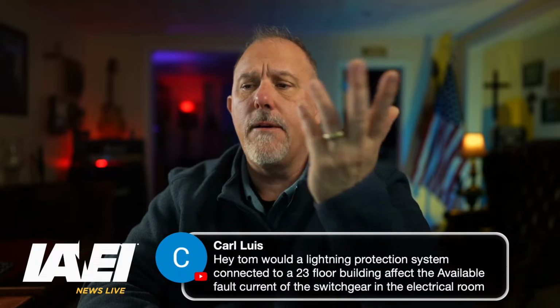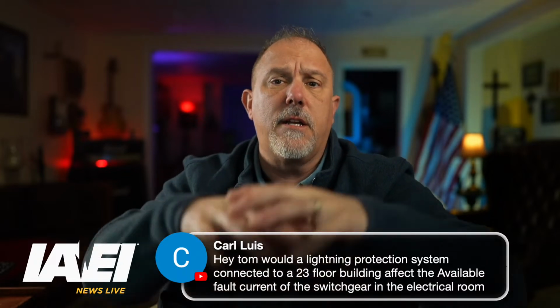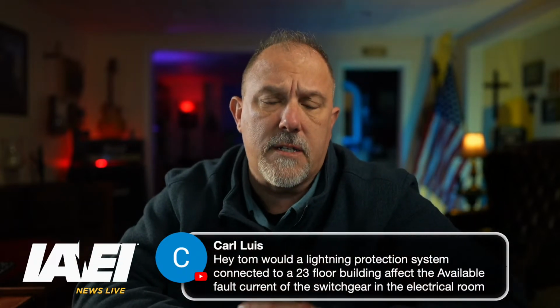Hey Tom, our lightning protection system connection to 23. The lightning protection system shouldn't affect that. It's completely separate because it connects to the ground of the system. I would not see that impacting the available fault current or the calculations at all because it's an independent system.